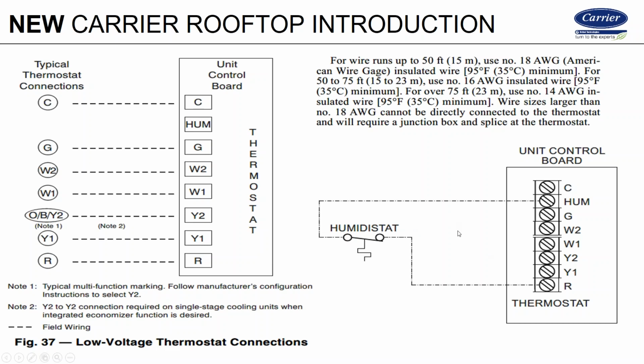This gives you some humidistat wiring. If you're using humidifier type units, that's a whole separate class. Up here are just some quick tips on wire sizing. Up to 50 feet, you can use 18 gauge, and you can see 50 to 75. We increase the size of 16, so 14 over 75. And that's nothing new with this unit. That's been around with rooftops for a while, so I just thought I'd throw that in there.